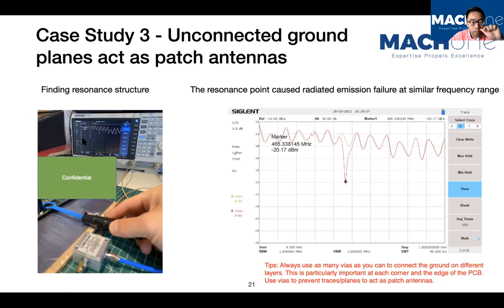But if you happen to touch a structure that has a very strong resonance frequency, the energy rather than being reflected back will be absorbed by the resonance structure, so you'll see a dip. In this case, we identified on the edge of the PCB, where the TO247 is mounted, a very strong resonance point, and that actually aligns with the radiated emission test - at that point you see a big resonance peak.